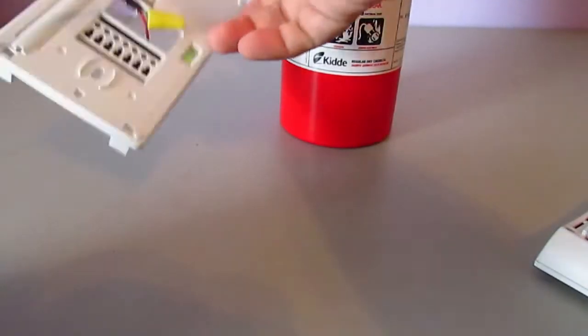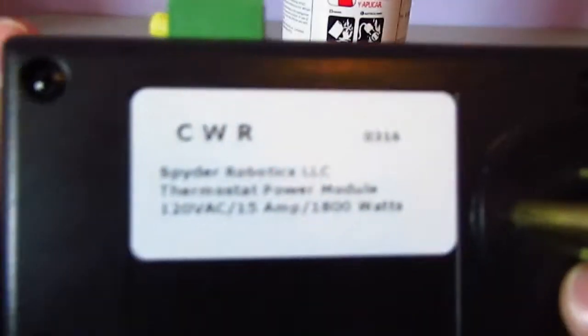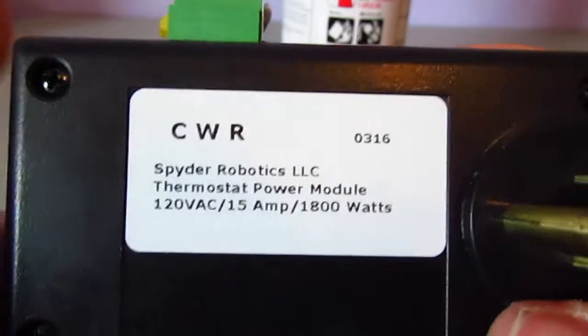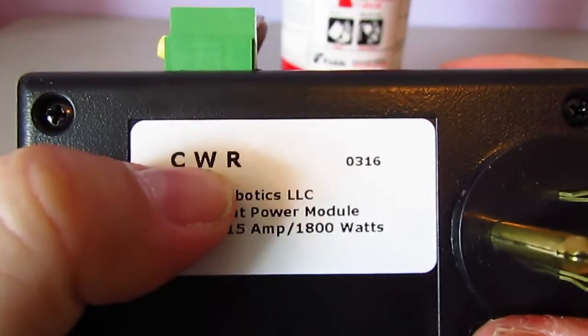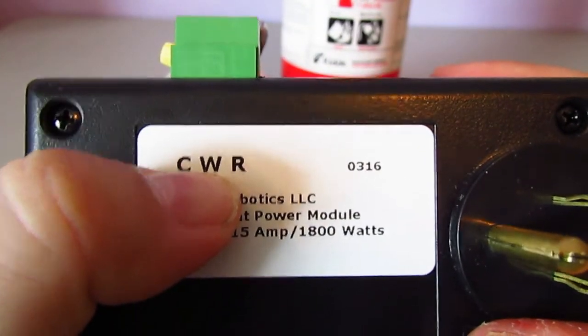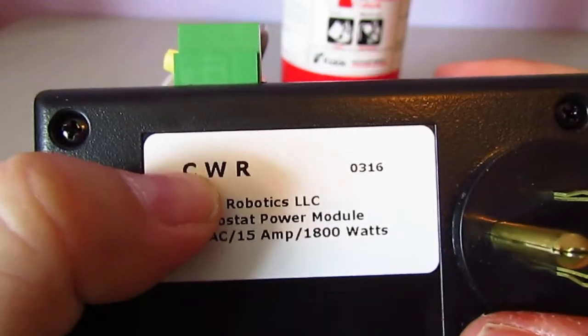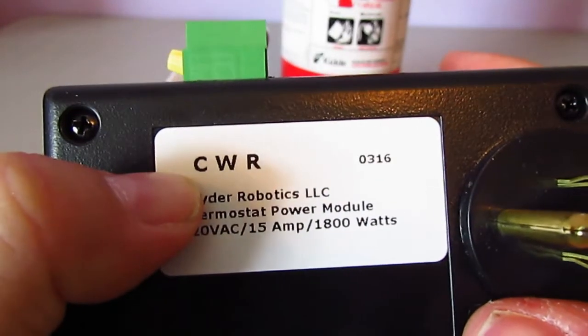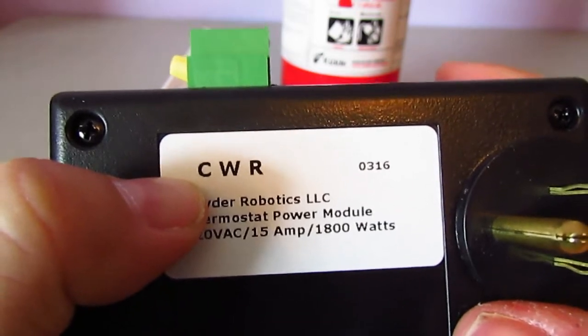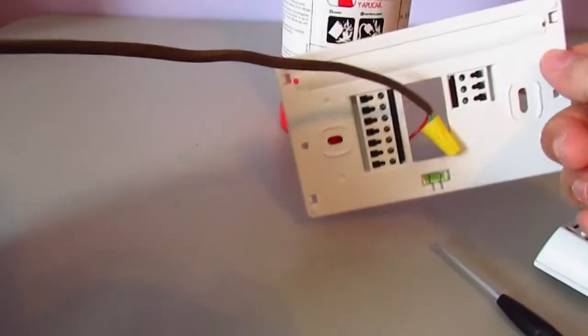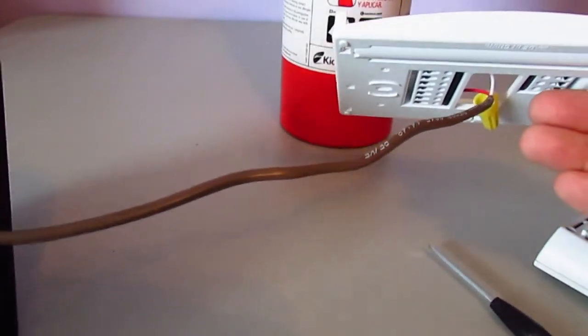So here I'll be using RH and W. Cap the green. And then we look at the power module. See right here. Similar naming convention. Red. So if it's RH or RC either one gets put into R. W is white and then C is the common. So if you need to use C to power something without batteries you can do that.